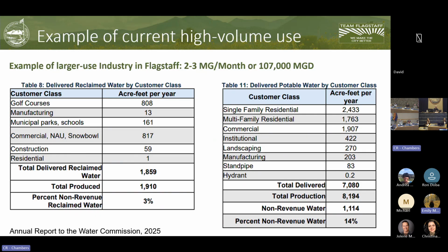So there are different ways we can maximize efficiency, requiring sub-metering to make sure that if they have faulty valves, there aren't leaks going unattended to. We can maximize the cycles of concentration in the cooling system. The maximum efficiency is about 7 times you can reuse the water before you have to dump it, because it has been mineralized to the point that it will damage the cooling tower, and those are very expensive.